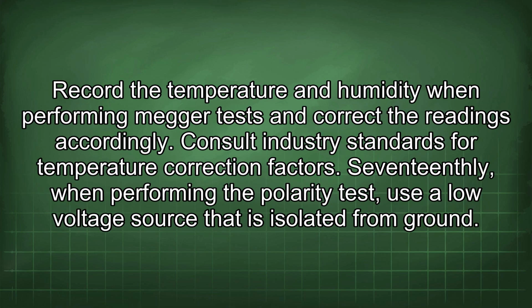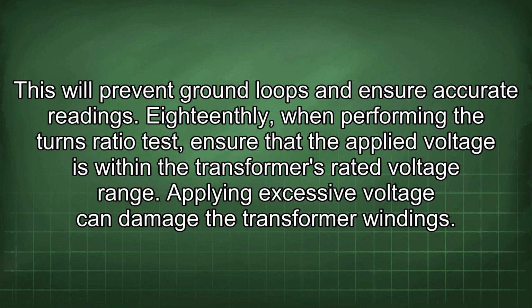Record the temperature and humidity when performing megger tests and correct the readings accordingly. Consult industry standards for temperature correction factors. 17thly, when performing the polarity test, use a low voltage source that is isolated from ground. This will prevent ground loops and ensure accurate readings.